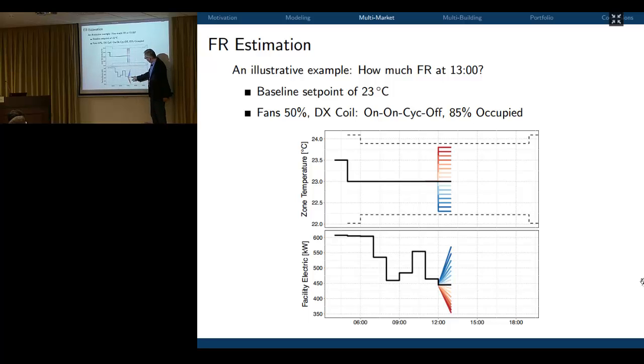Conversely, I could say 23 is cool enough and float my set point up, from 23 to 23.5, to 24, and so on — those upward movements. Now I use less energy: cooling more needs more energy, cooling less with higher set points needs less energy. So what have I achieved? Some load flexibility, simply by adjusting the set point.